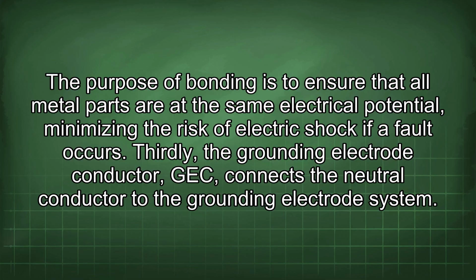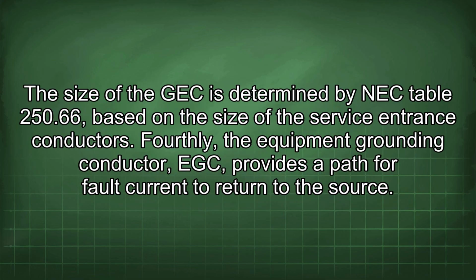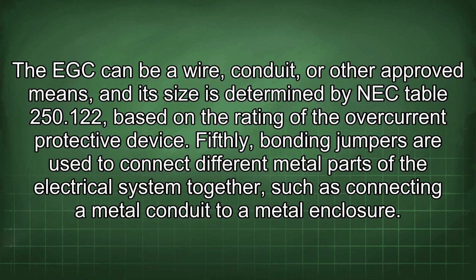Thirdly, the grounding electrode conductor (GEC) connects the neutral conductor to the grounding electrode system. The size of the GEC is determined by NEC Table 250.66 based on the size of the service entrance conductors. Fourthly, the equipment grounding conductor (EGC) provides a path for fault current to return to the source. The EGC can be a wire, conduit, or other approved means, and its size is determined by NEC Table 250.122 based on the rating of the overcurrent protective device.